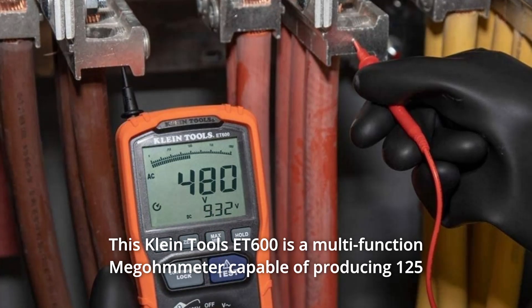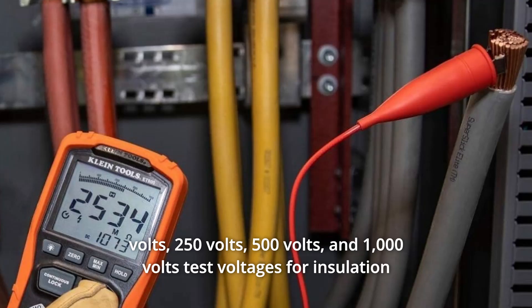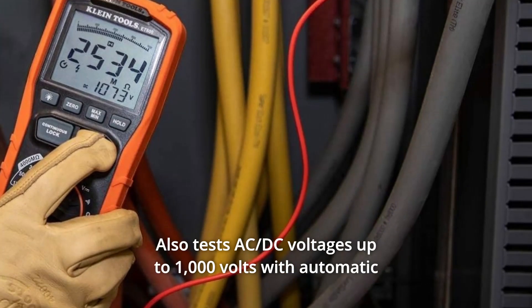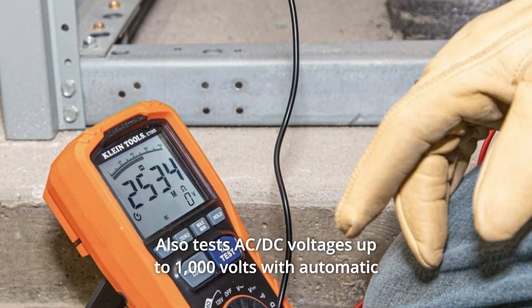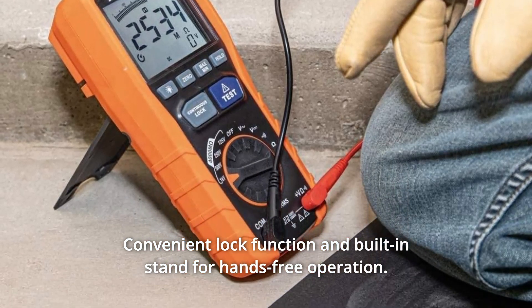The Klein Tools ET600 is a multifunction megohmmeter capable of producing 125V, 250V, 500V, and 1000V test voltages for insulation resistance measurements up to 4000MΩ. It also tests AC/DC voltage up to 1000V with automatic ranging true RMS technology, a convenient lock function, and a built-in stand for hands-free operation.